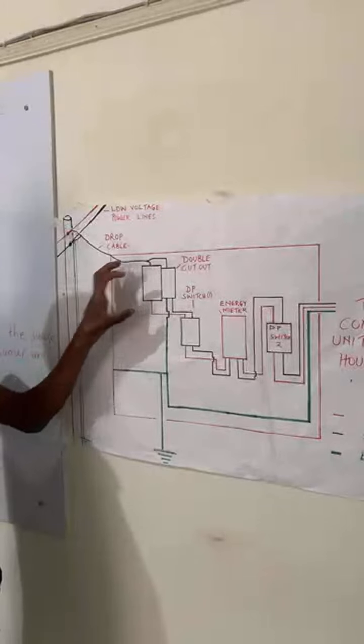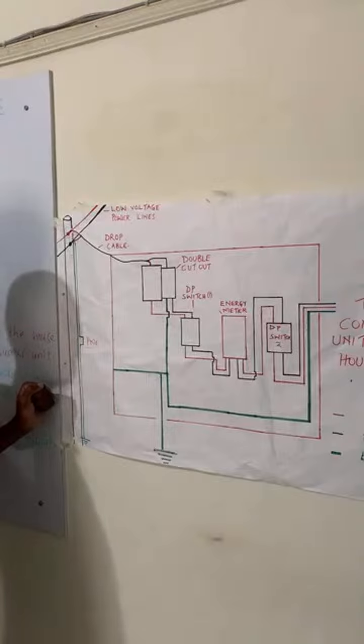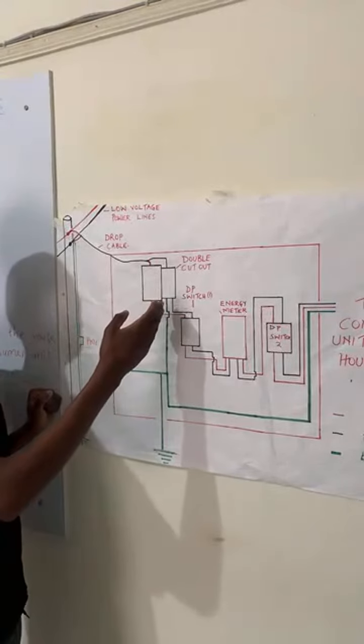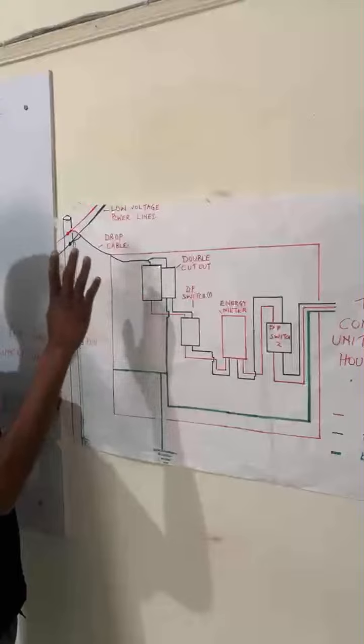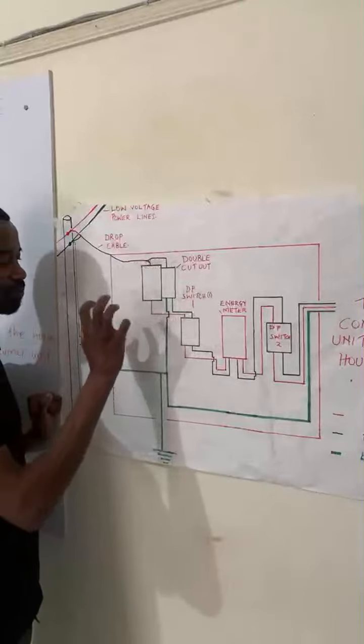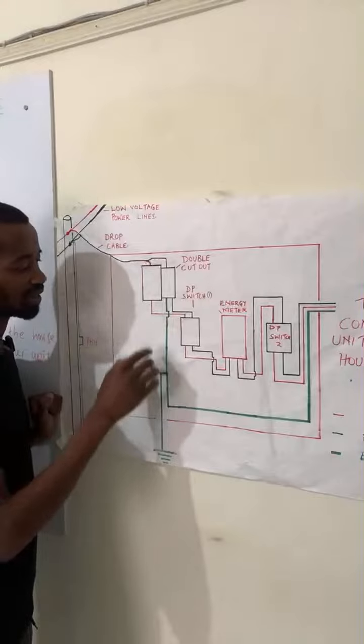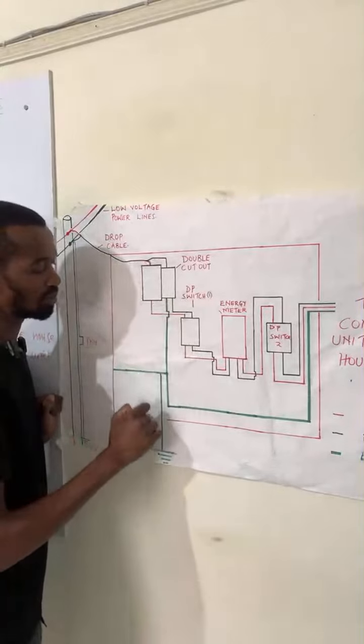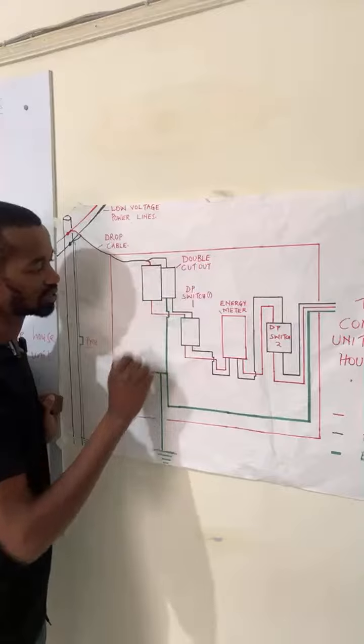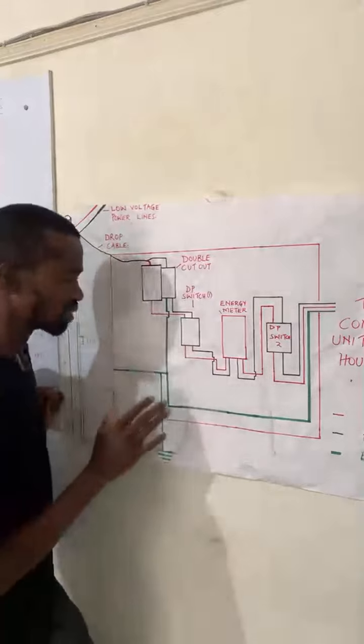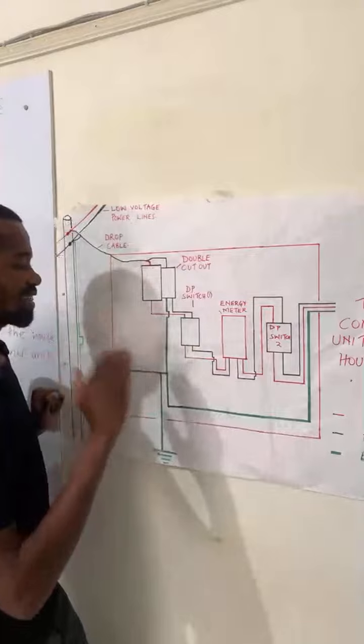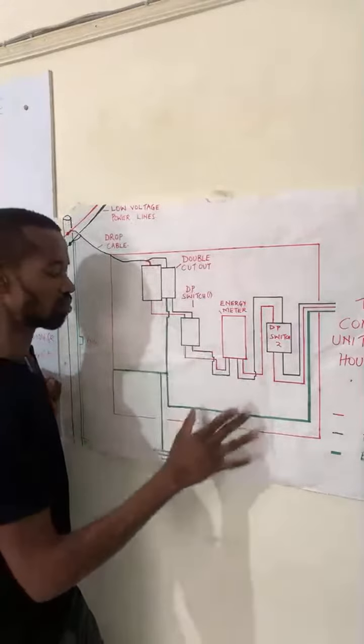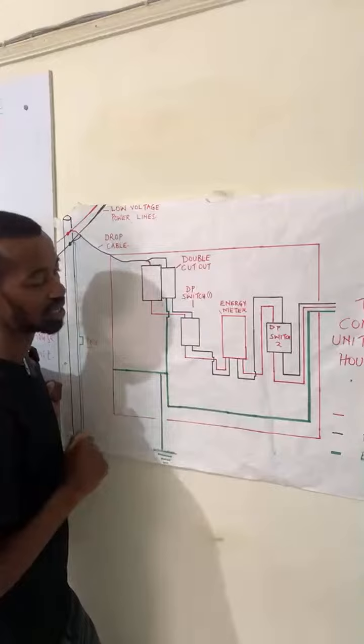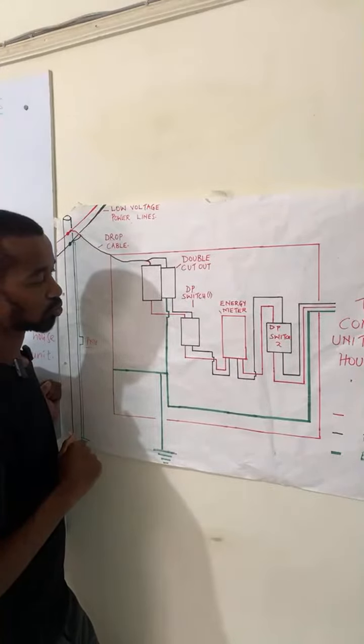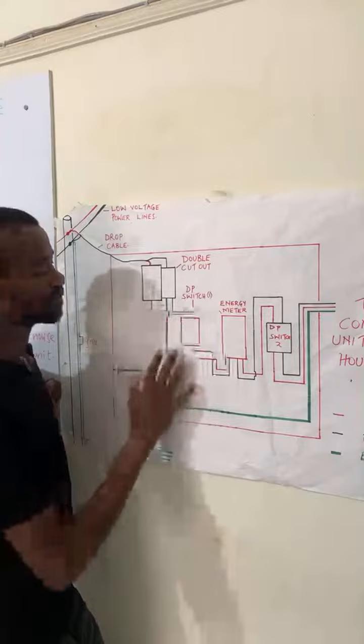Yeah, so when we get to this particular point, it is very important for us to spend a minute there. We may have a double cutout or a single cutout. Here, earthing plays a crucial role. If the earthing is not well done here, or there is an issue with the earthing at this point, there is a problem. But this one is a demonstration for meters that are connected at the meter box. When we get to pole mounted meters, we will have a different scenario there.